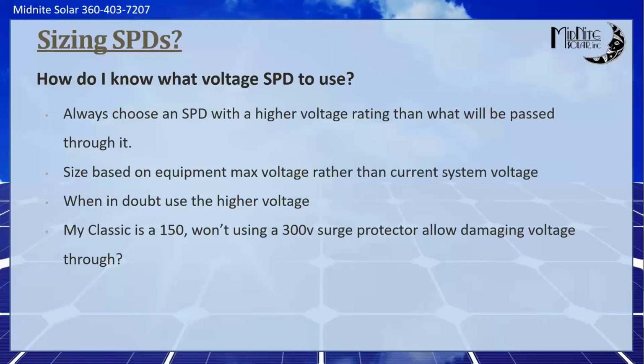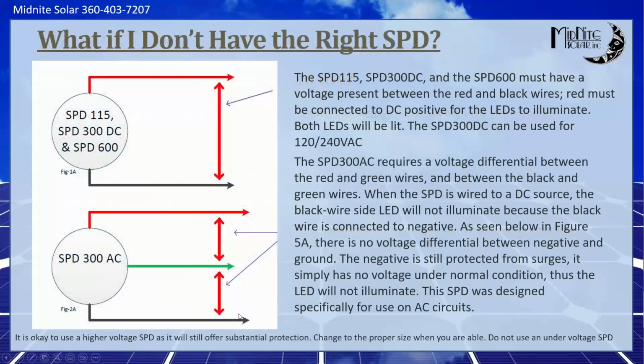The other one that you'll get is, why is there an AC and a DC 300? And long story short is, we used to not have an AC and a DC model. We had a 115, a 300, and a 600. They all lit their LED like this one down here, and basically, on an AC system, they would use voltage between the red and the green to light up one LED, and between the black and the green to light up the other LED. Now, if you put that on a PV array, of course, there's no voltage between negative and ground. So we'd only have one LED on in the SPD.